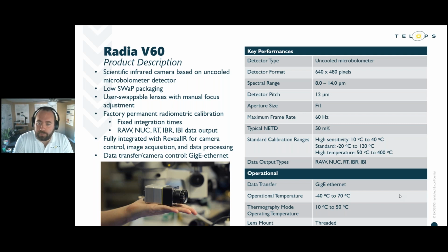The V60 is delivered from the factory with a fixed integration time multi-point calibration. This is going to enable calibrated measurements across 3 different temperature ranges, which you can see below here. It also is going to allow the data to be displayed in units of digital levels, radiometric temperature, in-band radiance, or in-band irradiance, just like Telops' traditional calibration. Camera control and acquisition is going to be handled by Telops RevealIR software. We have full integration into that software package. And data management is going to be handled through a GigE Ethernet connection.